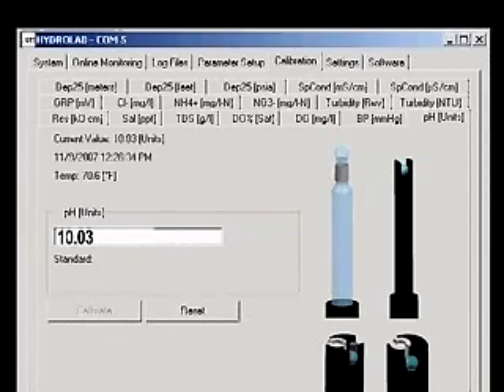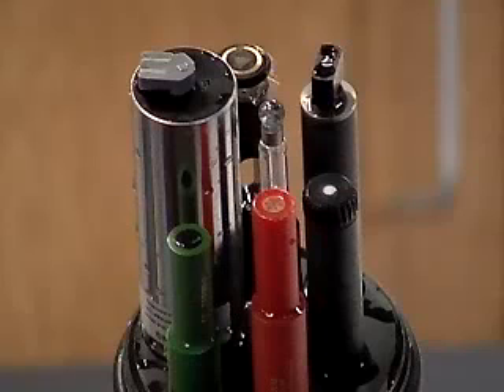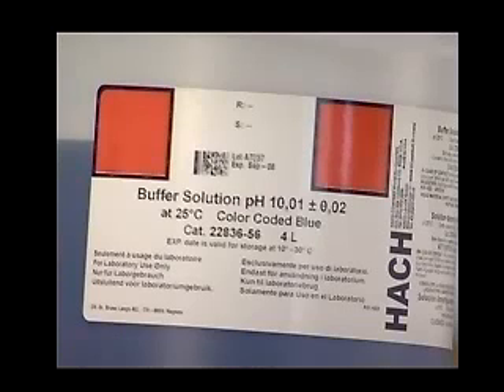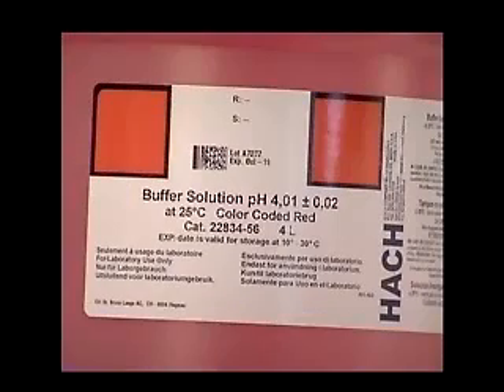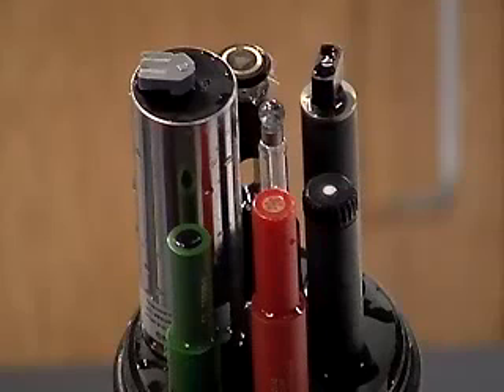If the pH readings continue to drift for an extended period of time or jump up and down, the sensor may need to be cleaned or replaced. The pH sensor is now calibrated. If desired, a linearity test may be performed with a buffer opposite that used for pH slope calibration. For example, if pH 10 was used to calibrate, check with pH 4, or if pH 4 was used to calibrate, check with pH 10. Repeat the process used for the previous calibration with the opposing buffer solution, but do not click the Calibrate button again.